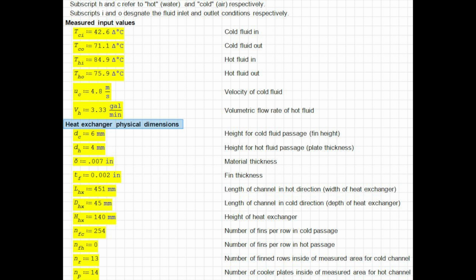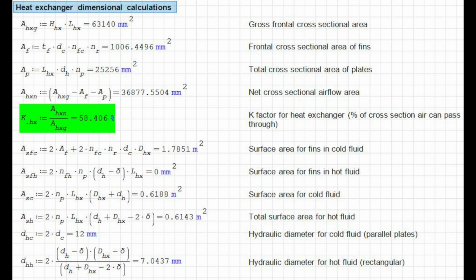Next we move to the dimensional analyses. This is where we get the gross cross-sectional area: how big is the front of the exchanger total, how much area is the fins, how much area is the plates, and what is the net cross-sectional area. You divide the net over the total, and then you get your K-factor. Our K-factor for this one came out to be 58.406%.